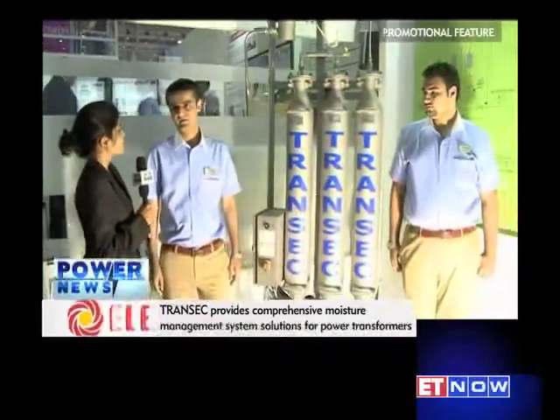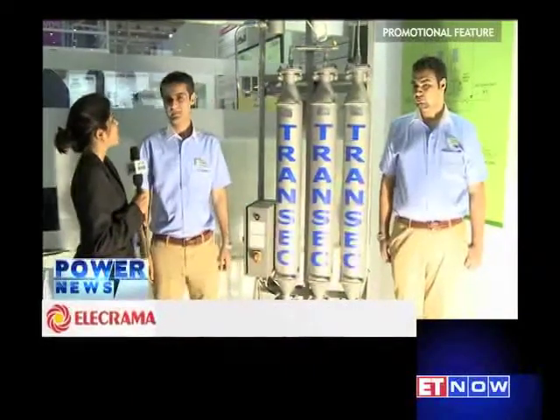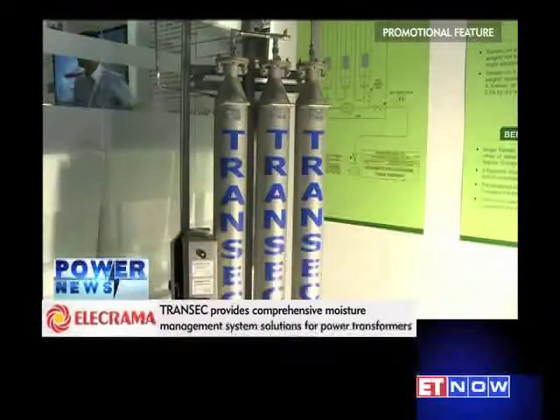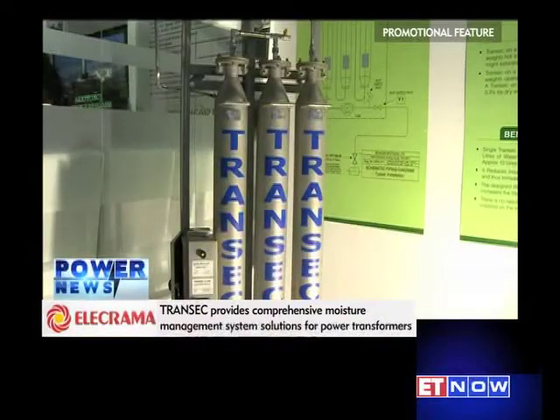How does this TRANSEC system help remove moisture content from a transformer, and how does it enhance performance? This TRANSEC system, manufactured here in India, is installed on a transformer where the transformer oil is fed in through the bottom of the unit. It passes through a sensor which gives an input ppm reading along with the temperature.